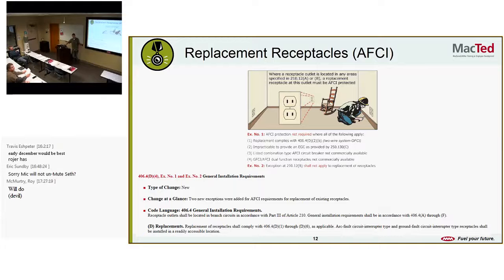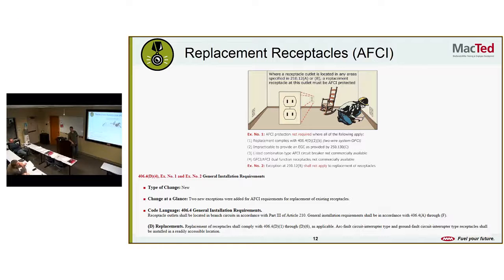Not real sure on that one. Looks like... I don't know. Any ideas on that? Well, what they're showing in that picture is a 2-wire. Oh, so if you don't have a ground, it would have to be a GFCI receptacle still, because an arc fault needs a ground. Yeah, and that arc fault wouldn't work there. Okay, so there we go. So if you have a 2-wire, you don't have to put an AFCI in there. You can get by with a GFCI.